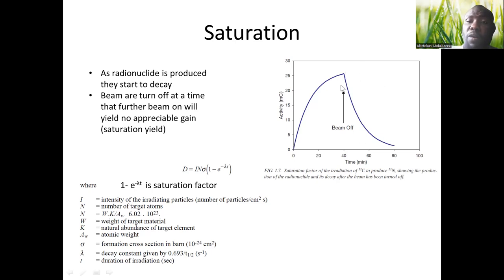So we normally say the optimal running time for this is around 45 minutes. So we stop the beam at this point. I see a drop off.